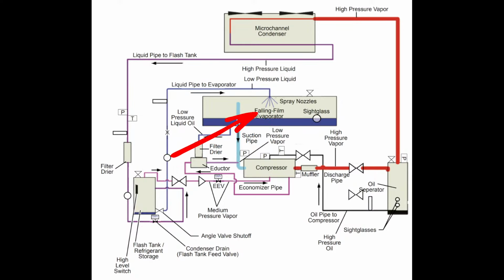So I'm honing in on this because this will be a key point here in a minute. So we have a falling film evaporator, and then we come back out into the suction, back to the compressor. So again, this is a Style A. The oil circuit itself is basically the same. So we have our eductor line pulling off, sending oil back to the suction line on this particular system.